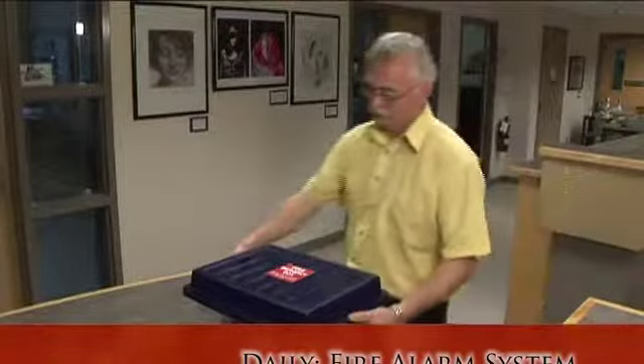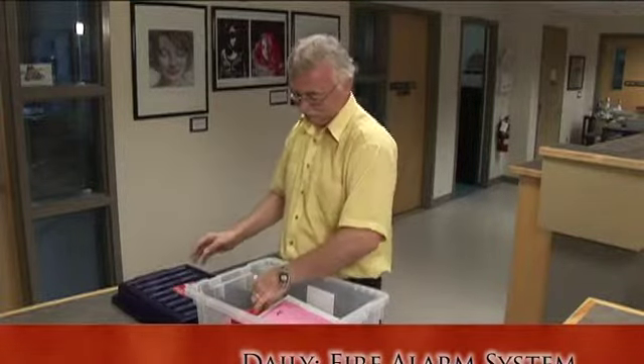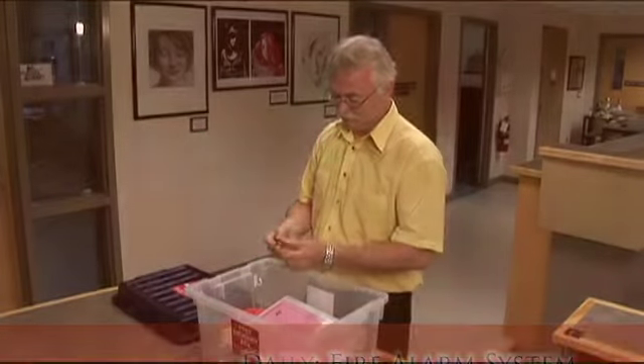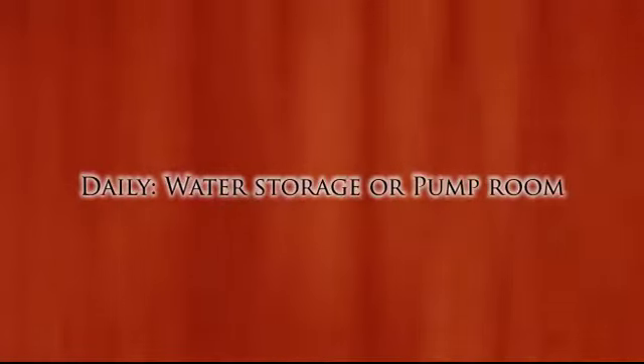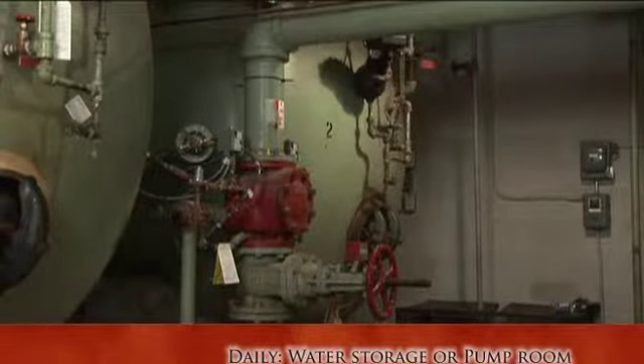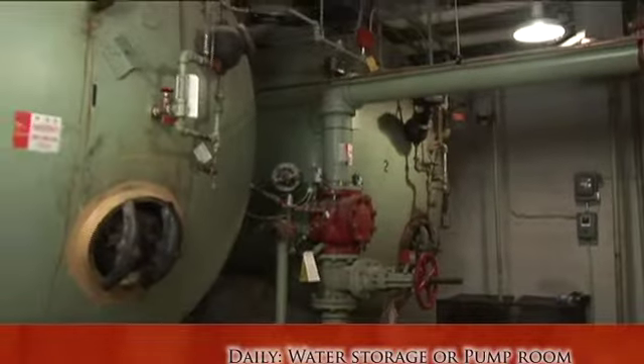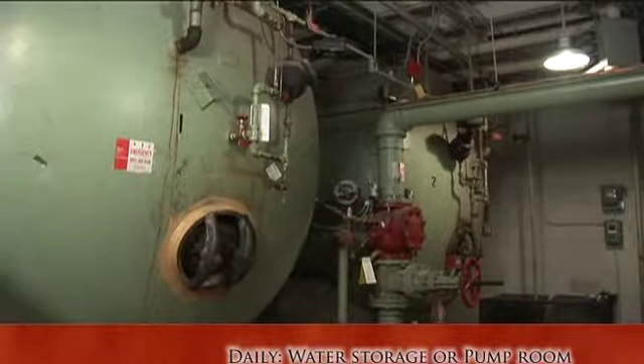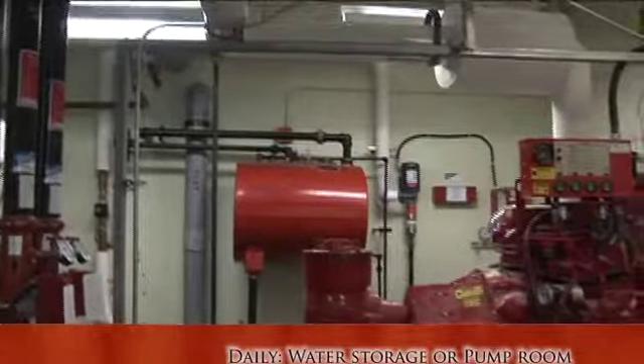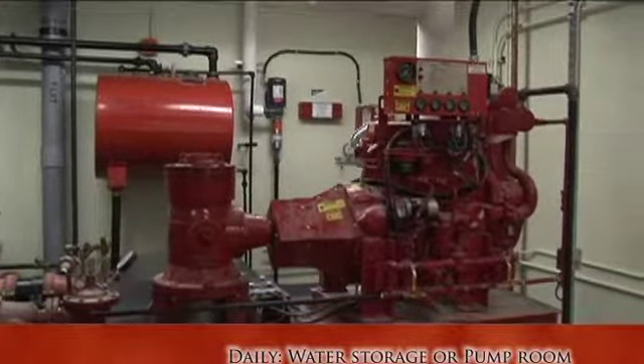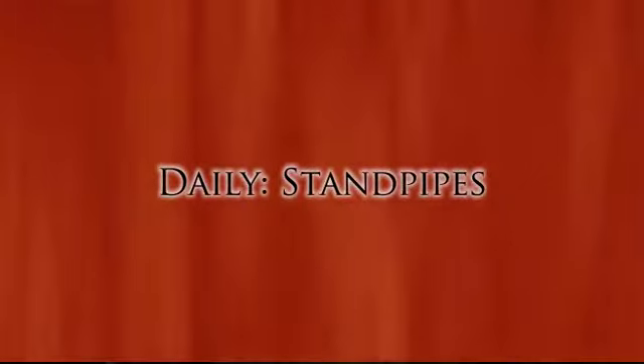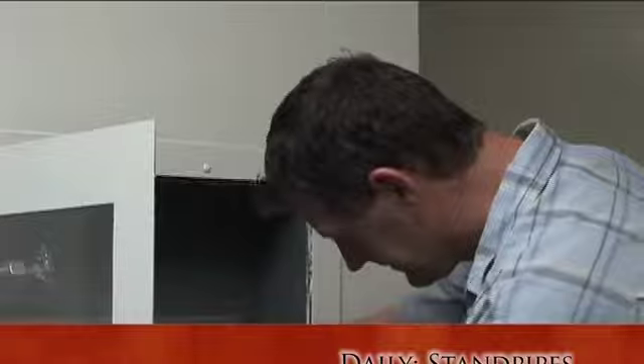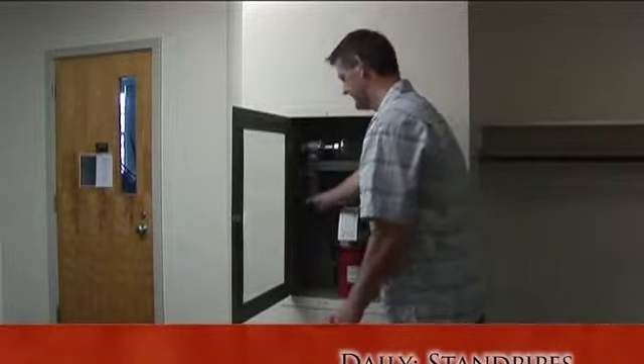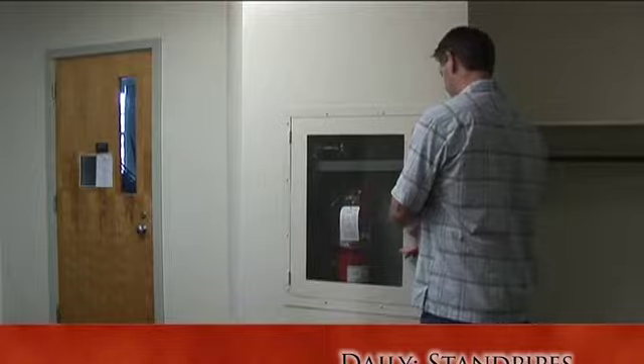Now, always check daily to ensure the alarm system keys are present and easily accessible. The temperature of any room containing pressure tanks or reservoirs for the sprinkler system, if you have them, needs to be inspected every 24 hours during freezing weather to make sure that it does not fall below 4 degrees Celsius. If your school has them, inspect the standpipe and the hose cabinets for noticeable deficiencies. If you find something wrong, you should notify your supervisor that corrective action is required.